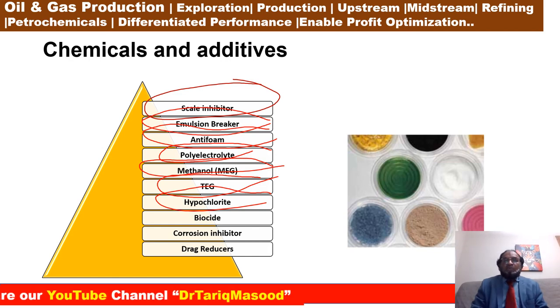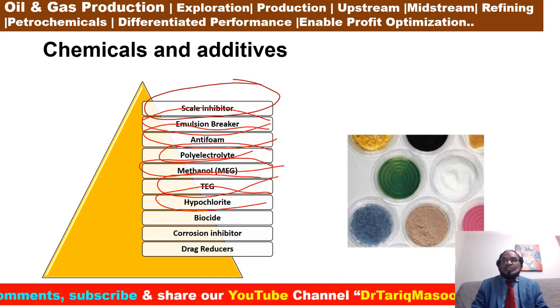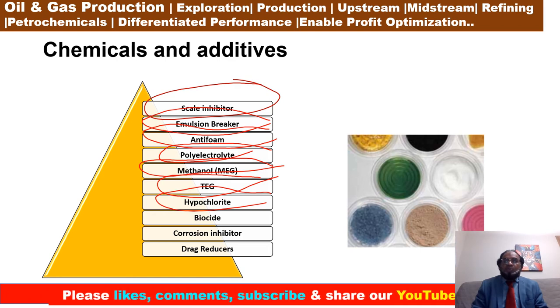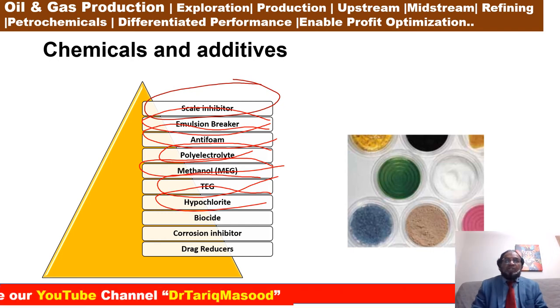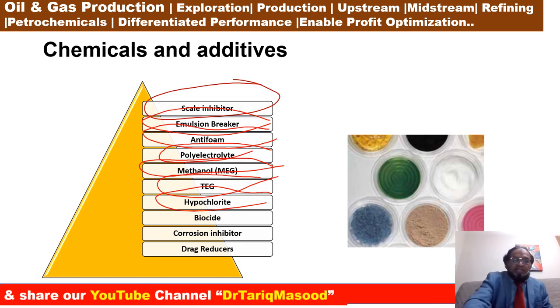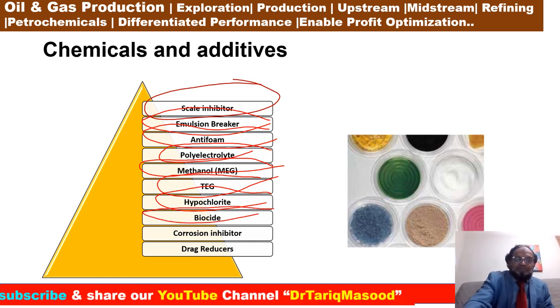Okay, the next is hypochlorite. Hypochlorite is added to seawater to prevent the growth of algae and bacteria in the seawater heat exchangers. Hypochlorite is produced by electrolysis of seawater to chlorine. In one variant, copper electrodes are used, which adds copper salts to the solution that improves effectiveness. Okay, then next is the biocides.